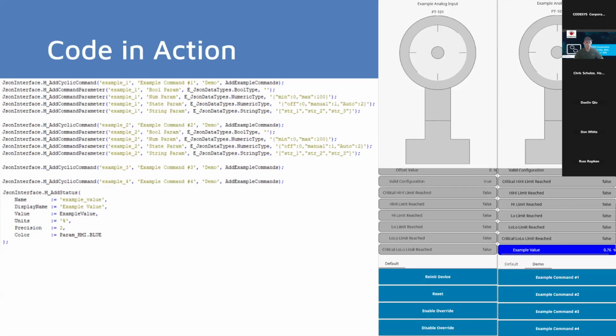For getting things to show up as HMI status tags, we've added this add status method. It adds the example value tag, in this case, to the HMI and lets you decide what color you want. So if it's an error, it's very easy to do a little select statement and just toggle it between gray and red. Easy. It lets you bring attention to items on the HMI and maintain a very consistent color scheme, since your color source is posted from the PLC side. It saves a significant amount of time, since you don't need to create new buttons, new tags, new faceplates, none of that. It's just added in the PLC, good to go. And because we apply this to our library, a VFD is always going to have a speed feedback, which we're always going to want to see on the HMI as a status. It comes standard with our library, so we always have it available. It makes it very, very simple to implement.